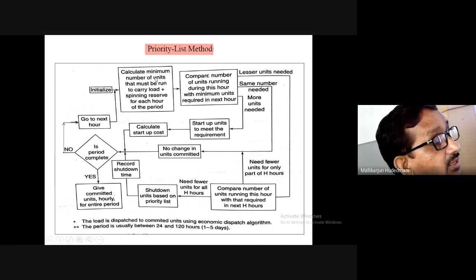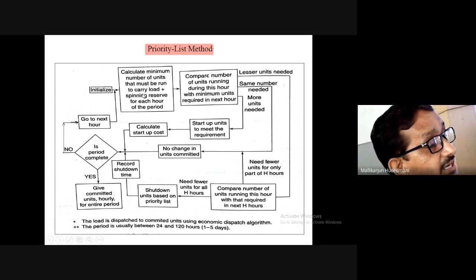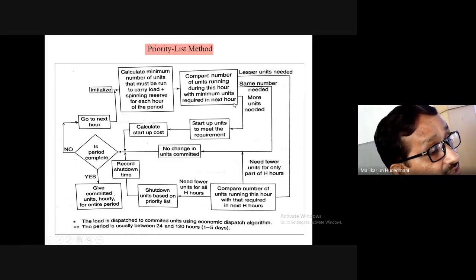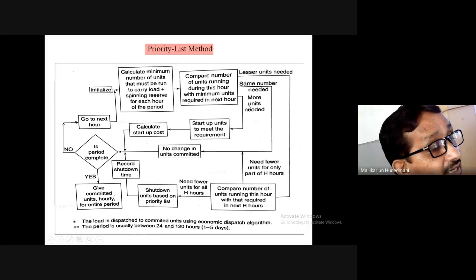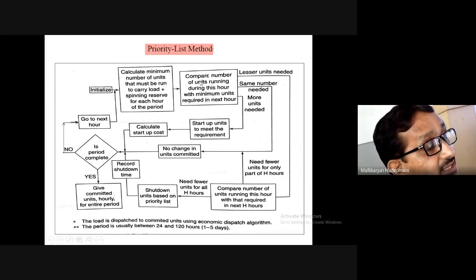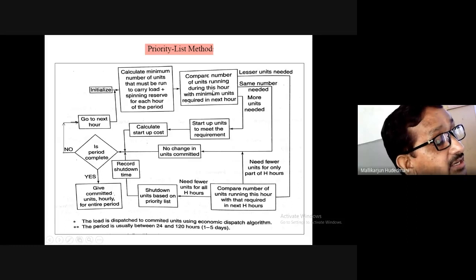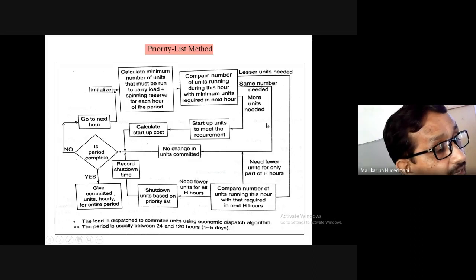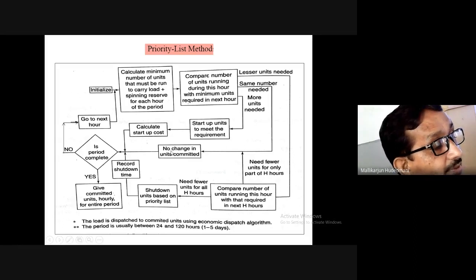During this 9th hour, how many units are running? Is that capacity of generation and the reserve perfectly okay? Then check, is the current 9th hour setup requiring an additional generation, or to maintain the same thing, or to reduce the generation? Again, I take a decision. Let's say in the 9th hour there is no incremental change, it is maintained. Then I may go this way, the same number of generators I maintain. I come down, no change in commitment.